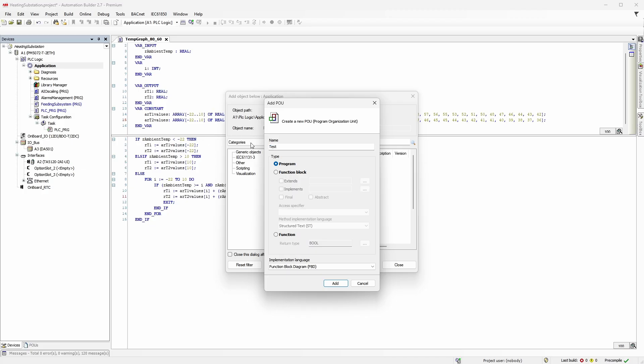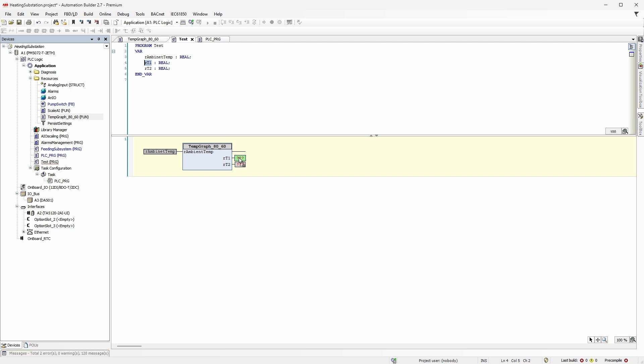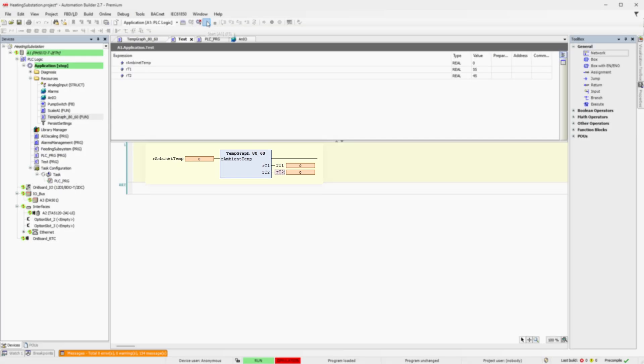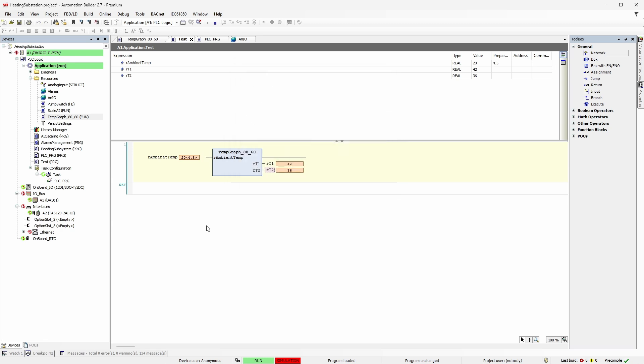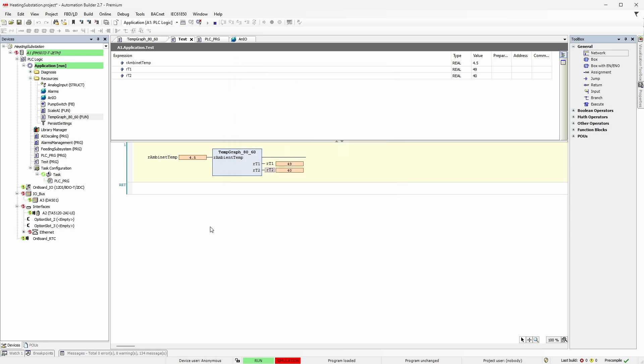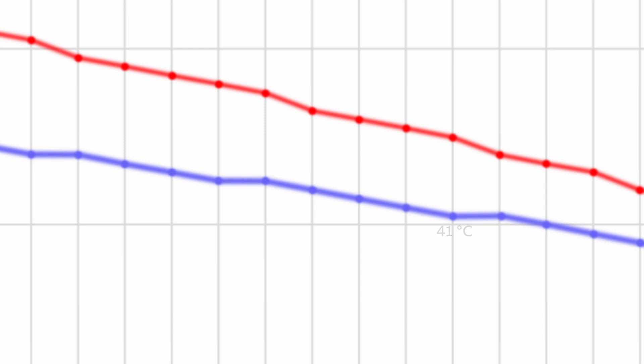Let's test the function. Add a POU for testing, call it in PLC_PRG, and add a function call along with some test input and output variables. Go to simulation and switch it to run. You can see that it already works: 55 and 45 degrees are exactly the values of T1 and T2 when ambient temperature is 0. Change it to something like minus 30 - okay. Now minus 22 - cool, works. Let's try 10 - and indeed it's 42 and 36. 20? Yes. Maybe something in between, like 4.5 degrees - and that doesn't seem to be right. It works for T1, but T2 value is wrong. Values for 4 and 5 degrees ambient are both 41, so anything in between must also be 41.